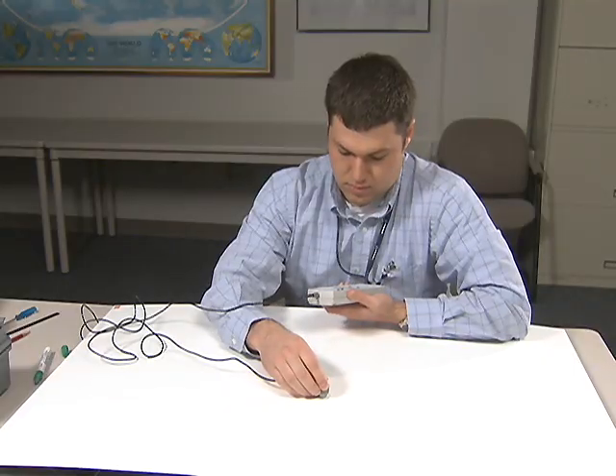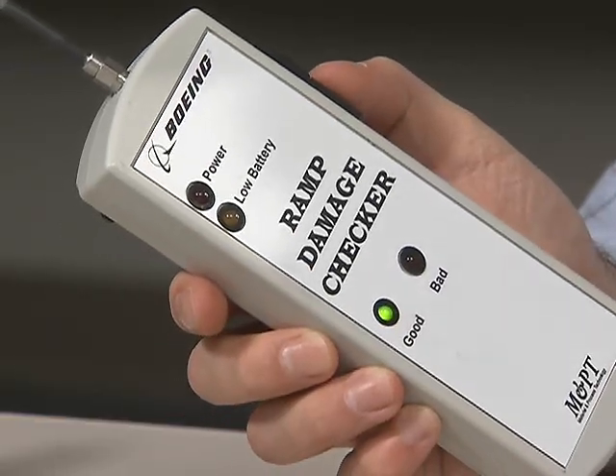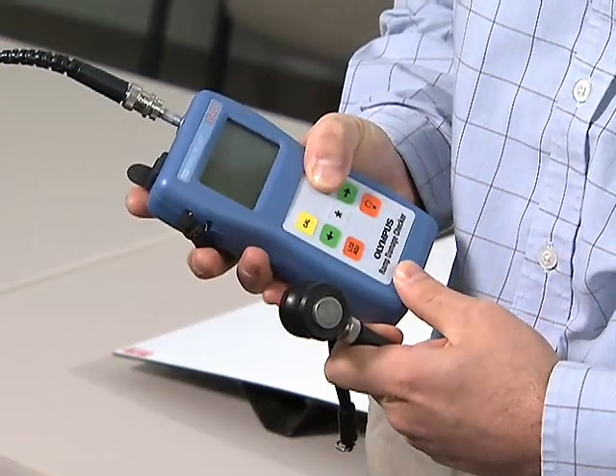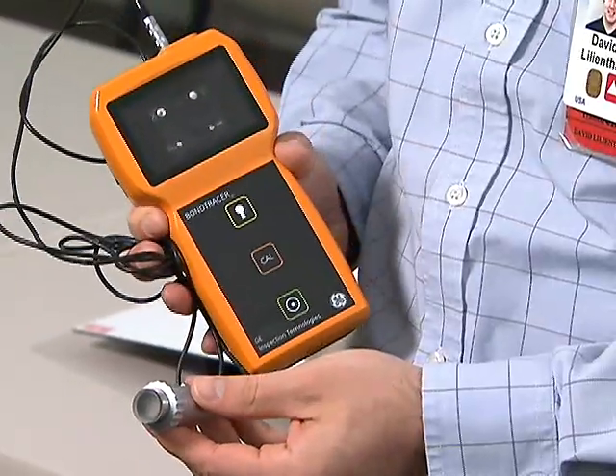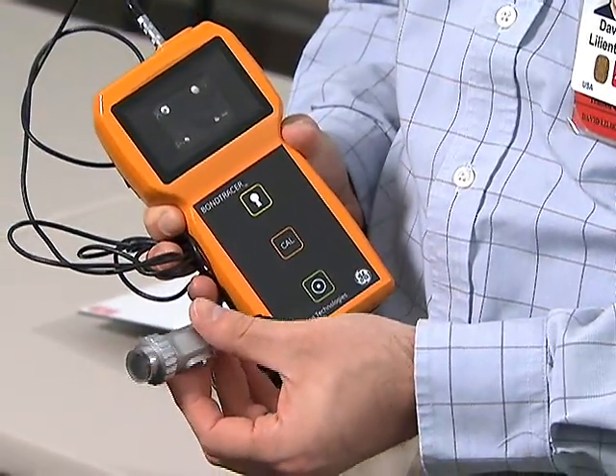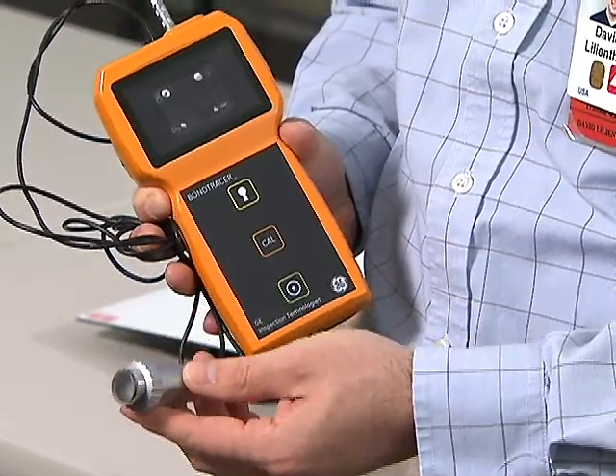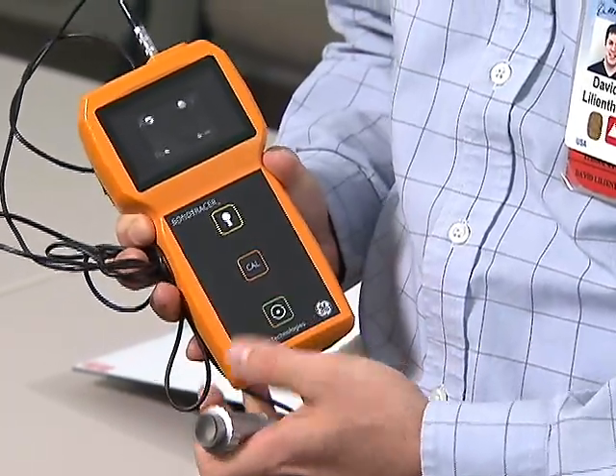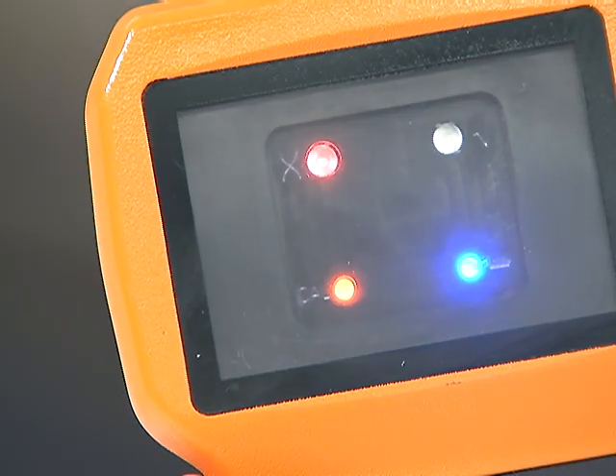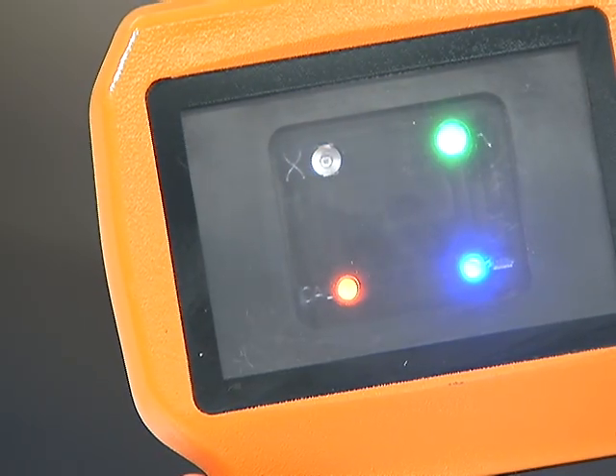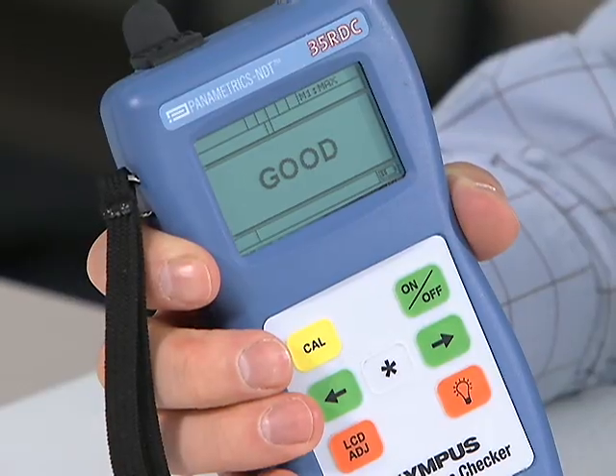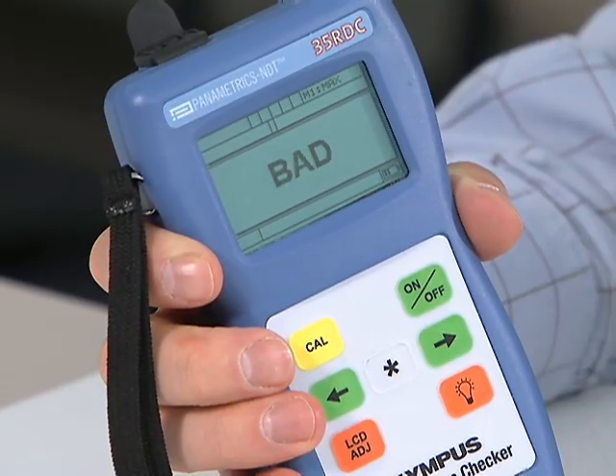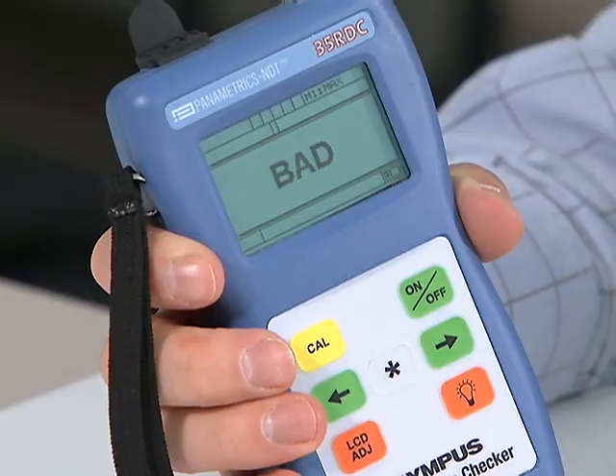The following reasons will cause the red light to illuminate. The RDC detects a delamination. Material thickness decreases by more than 1 ply. There is insufficient couplant between the probe tip and the part. The commercial versions of the RDC function like the Boeing prototype we have shown here, but there are some differences you should be aware of. First, the defect indicators are different. The GE Bond Tracer displays green and red lights corresponding to good and bad areas. The Olympus 35 RDC displays the words good or bad instead of a green or red light.